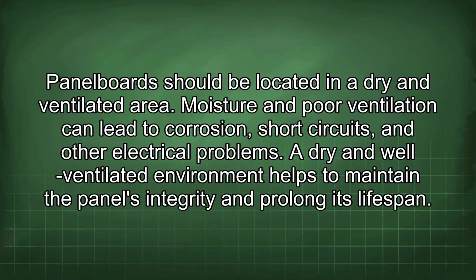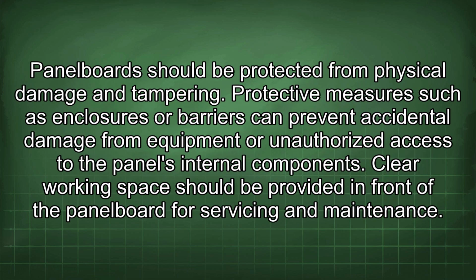Panel boards should be located in a dry and ventilated area. Moisture and poor ventilation can lead to corrosion, short circuits, and other electrical problems. A dry and well-ventilated environment helps to maintain the panel's integrity and prolong its lifespan. Panel boards should be protected from physical damage and tampering. Protective measures such as enclosures or barriers can prevent accidental damage from equipment or unauthorized access to the panel's internal components.